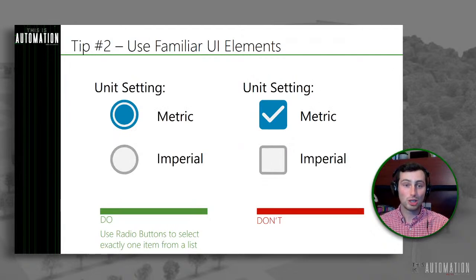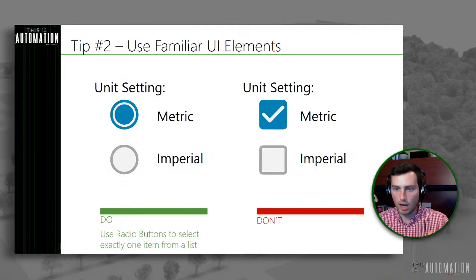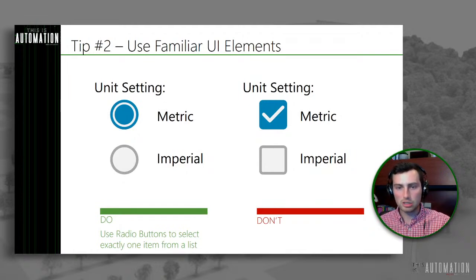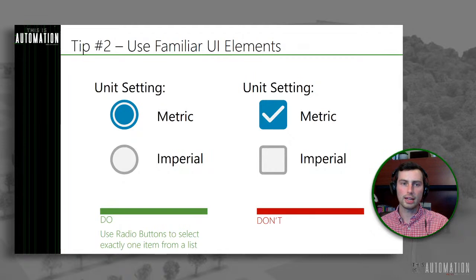The last one is an actual good use case for radio buttons — we've been giving them a hard time, but there are good use cases. When you want to select exactly one item from a list, that's where we use radio buttons. In this example, maybe we can switch units inside our HMI between metric and imperial. Obviously only one of those can be valid at any given time — exactly one choice out of a list. Perfect use case for a radio button. You would not want to use a checkbox here, since checkboxes allow multiple selections. And we certainly wouldn't want a toggle switch either, since it's for turning unrelated things off and on. That wraps up tip number two.